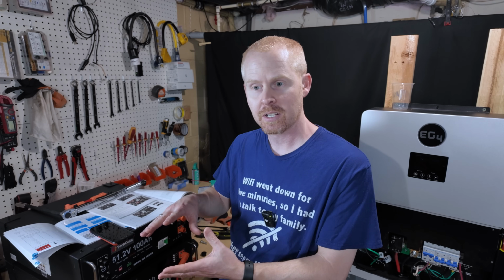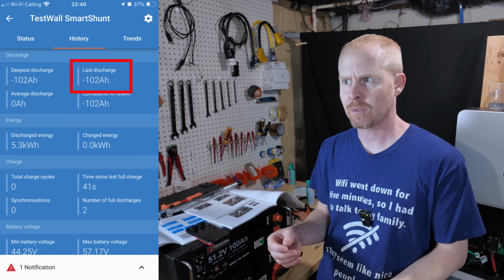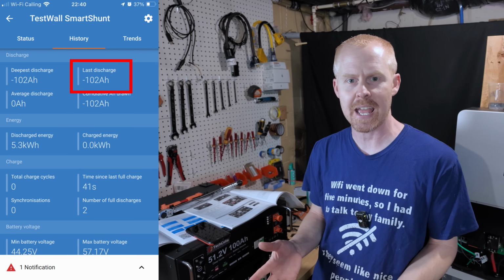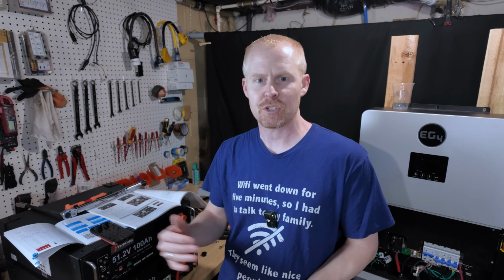So what ended up happening was it discharged all the way down, the battery said to turn off, and then the voltage leveled out. So then it was high enough that the battery turned the inverter back on again and started putting a little more power into my main battery bank. And that actually ended up doing 102 or 103 amp hour discharge.